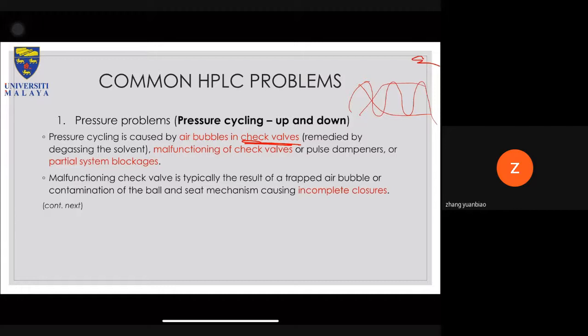Normally it is in the pump, because the pump is where the solvent capacity is the highest. As you go outside of the pump into the autoinjector or solvent mixture, or even the column and detector, the void volume in these other modules is very, very small. So even if there are trapped air bubbles at these other places, by just running your solvent flow at the normal rate, you will normally be able to excrete all the bubbles.